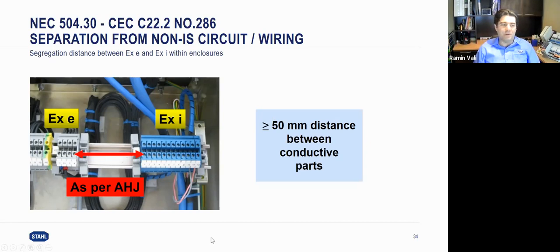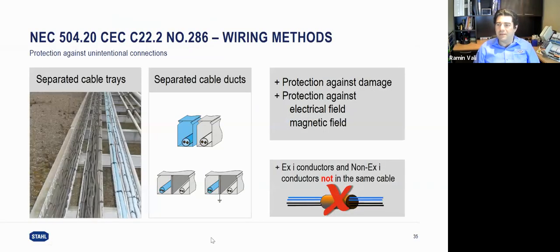There are some other wiring methods which are referenced in NEC 504.20 or Canadian Electrical Code section 286. This wiring method is basically to segregate or separate the IS cable from non-IS cable. We may be able to use them in the same tray, but those trays have to be mechanically apart, so the interference from the non-IS, high-powered signal should not be affecting the intrinsically safe cable.